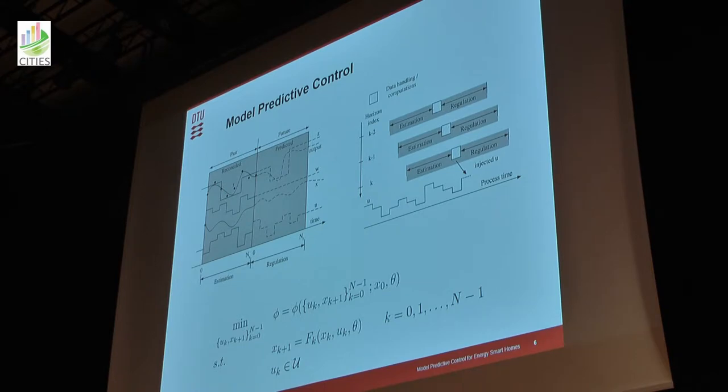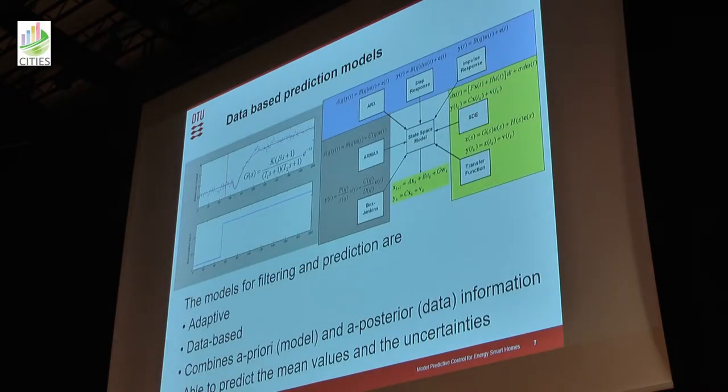It's based on the premise that you can solve an optimization problem very efficiently online and unsupervised, and also that you have models that are sufficiently accurate. Many of our models are data-driven. We have done a step response to get the model, and then this would be the transfer function describing it — it has a time delay, a gain, and time constants. We convert all these models into state space models, and then MPC works on these.